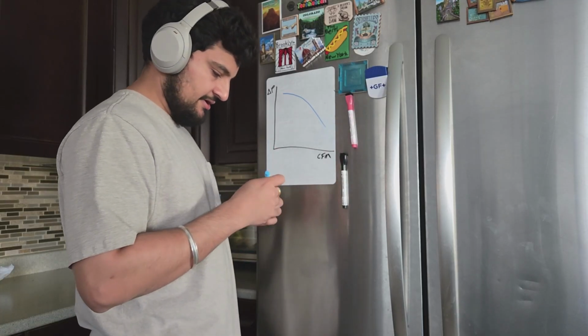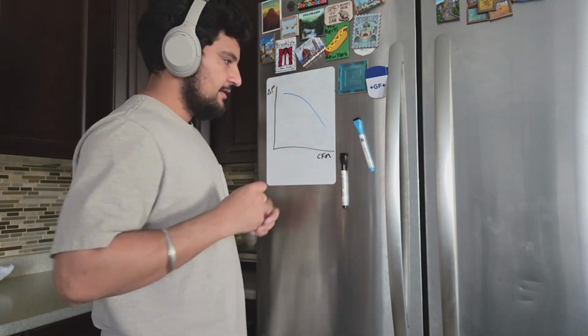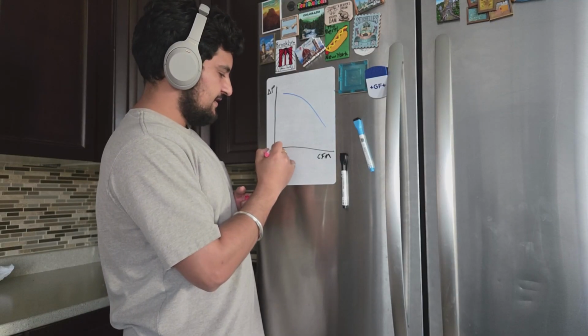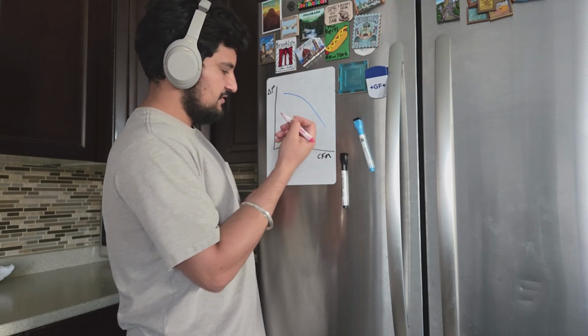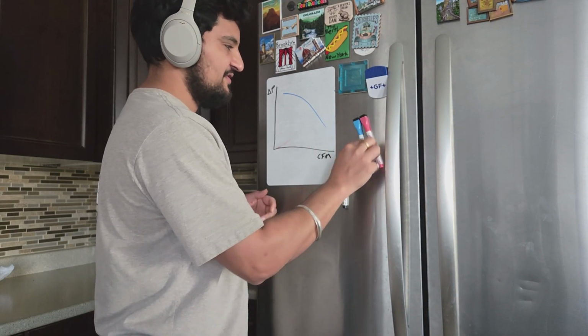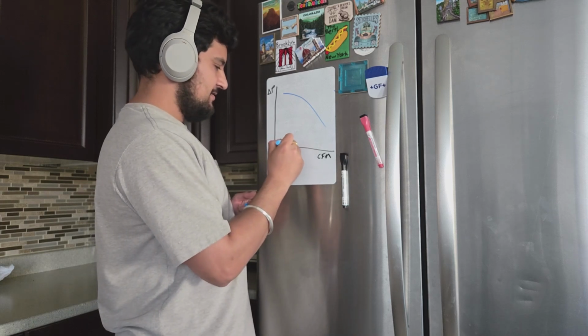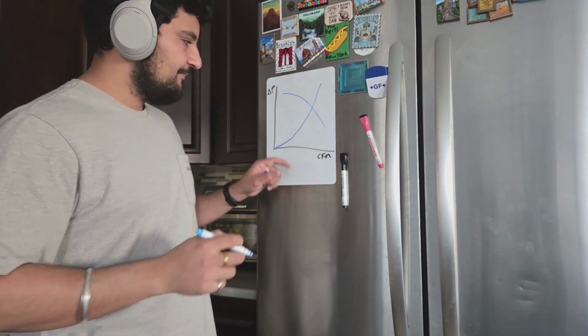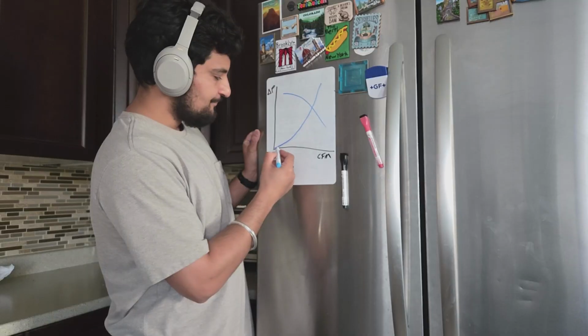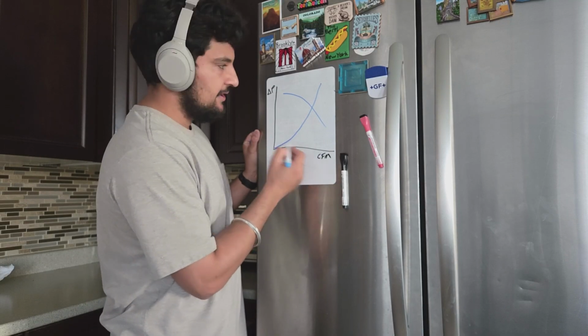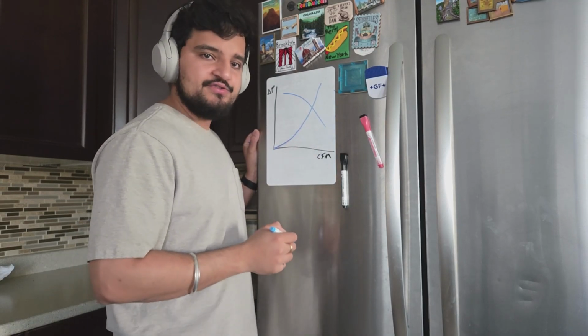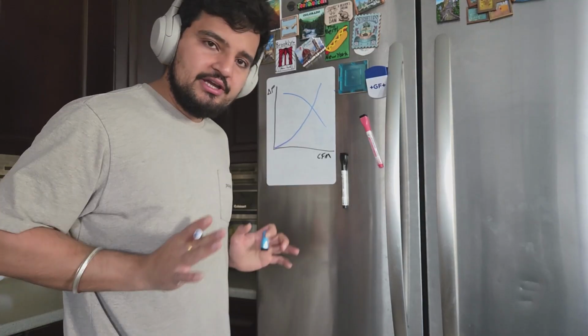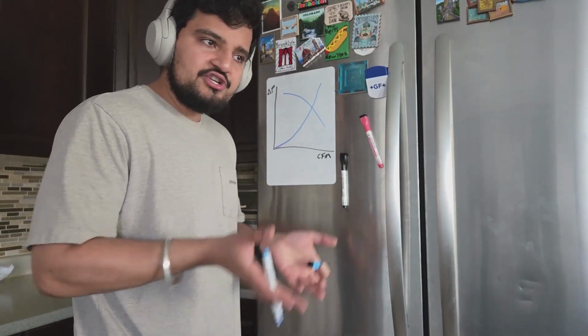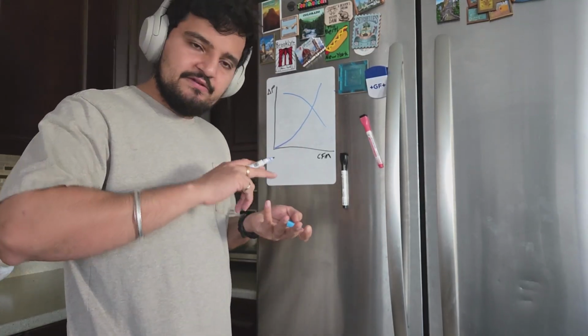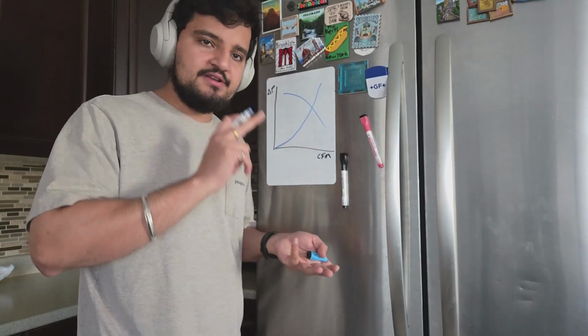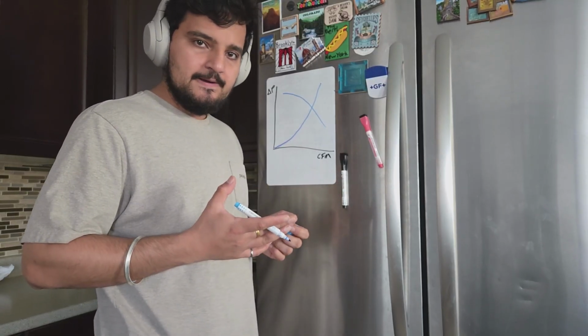Let's draw it on the pink highlighter. Your ductwork is something like this. No, the pink doesn't even work. I'll just use the blue. Something like this. In your ductwork, as your flow rate is increasing, the pressure loss is also increasing. The more air you're trying to push through that ductwork, the more pressure is being generated because of the friction loss, dynamic losses, losses through the filter, etc., right?